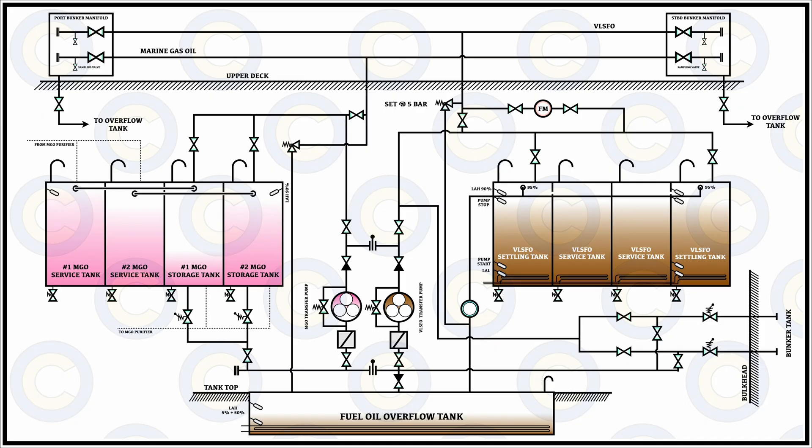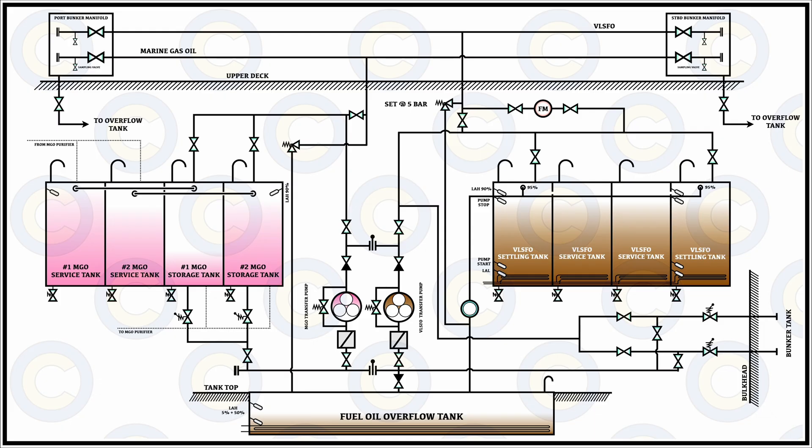Now once the bunker is received and all the lines are set back to normal, you can see that there are transfer pumps in the dedicated line available. These transfer pumps can draw suction from the dedicated tanks. For LSMG or gas oil you can draw suction from any of the storage tanks, and from there a dedicated suction valve would be available going into the diesel oil transfer pump which would again have a suction and a discharge. After lining up the pump by lining up the main suction from the tank, the intermediate suction and the suction and discharge valve for the transfer pump, you will again be having a final valve.